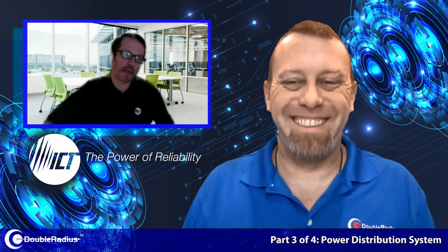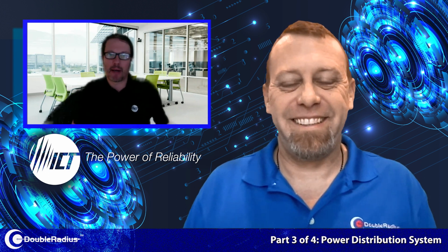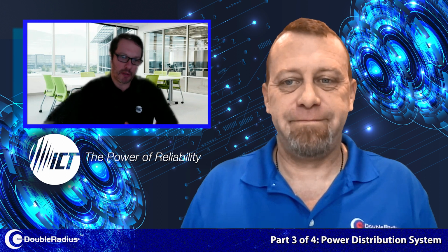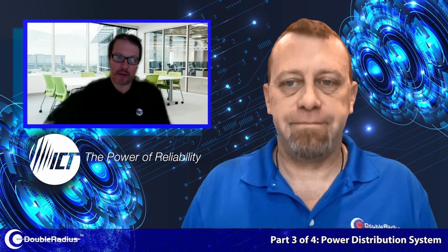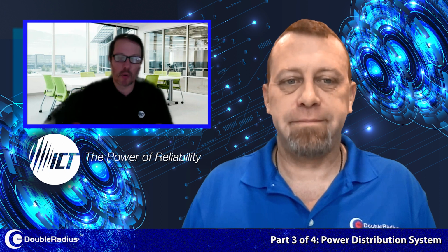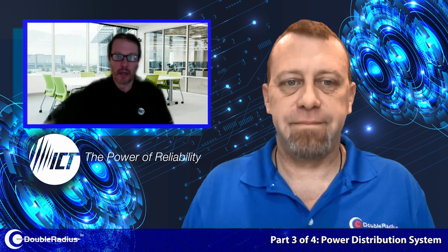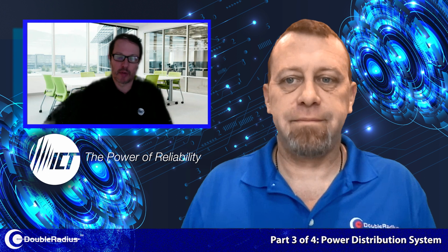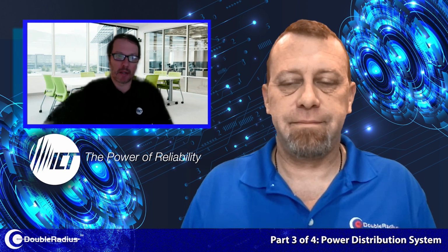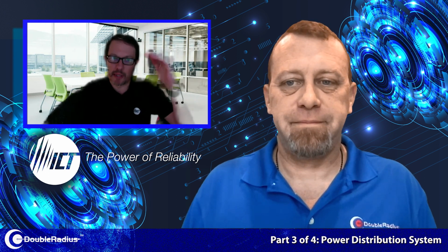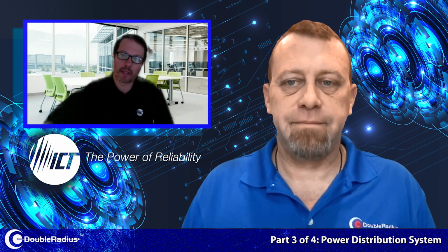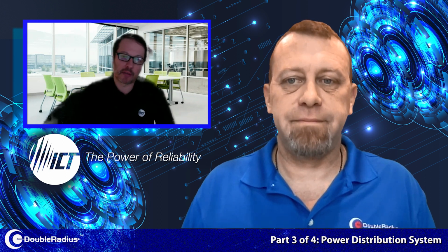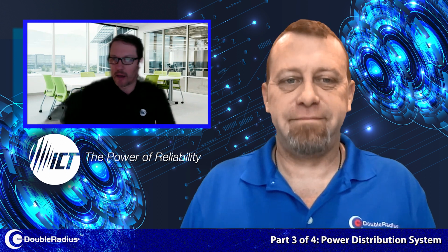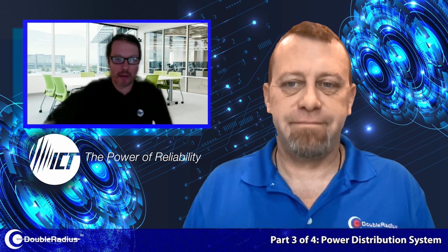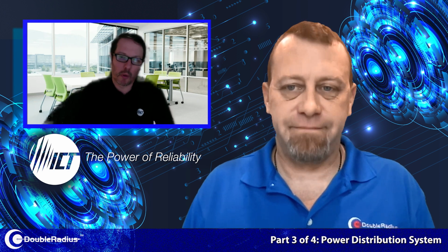In addition to that, a lot of these sites have battery backup. And so there's a certain finite amount of battery backup available, whether it's 8 hours or 4 hours or whatever you design your site to. So we also have load shedding capabilities. So if you're on battery backup and your battery voltage is slowly decreasing, we can have it where customers can pre-program our units to disconnect non-critical or non-essential loads at the site, whether it's a light or a lamp or a camera or some other non-network critical load.